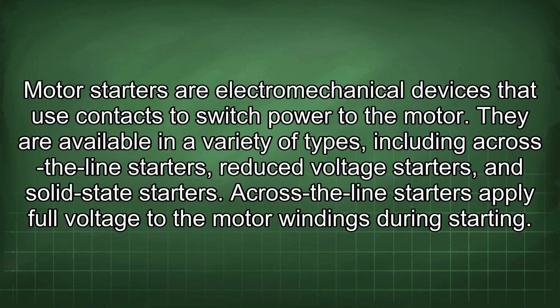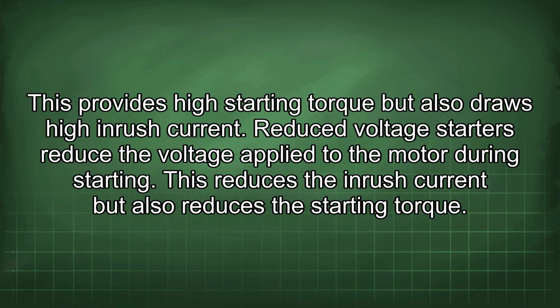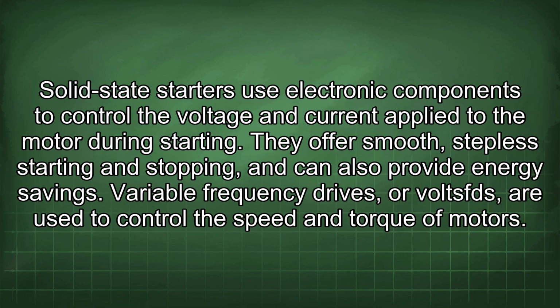Across-the-line starters apply full voltage to the motor windings during starting. This provides high starting torque but also draws high inrush current. Reduced voltage starters reduce the voltage applied to the motor during starting. This reduces the inrush current but also reduces the starting torque. Solid-state starters use electronic components to control the voltage and current applied to the motor during starting. They offer smooth, stepless starting and stopping, and can also provide energy savings.